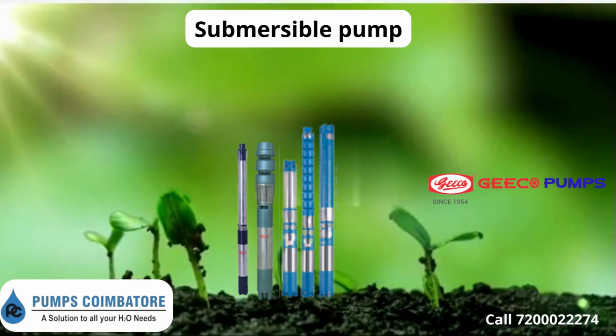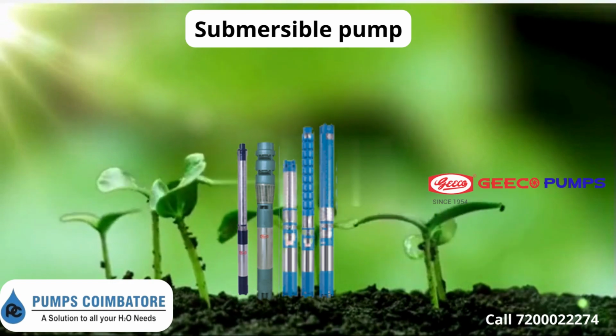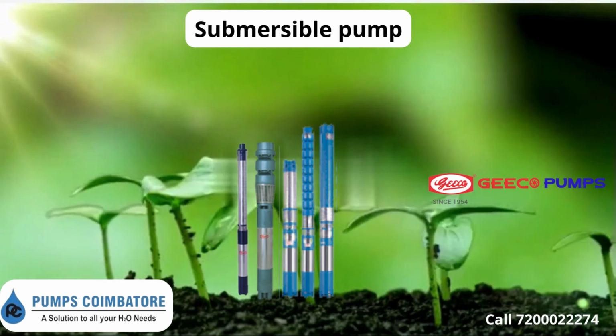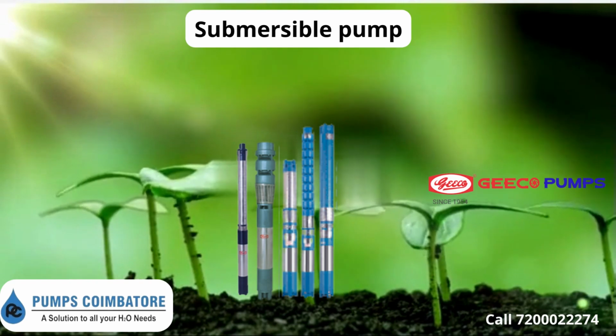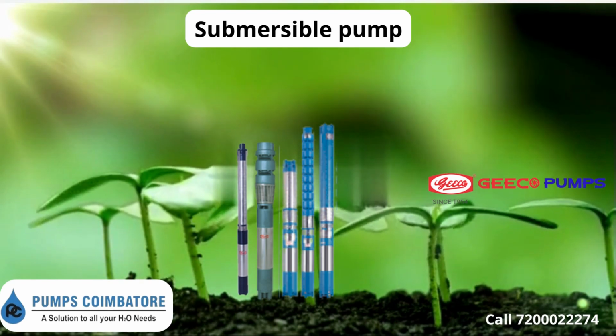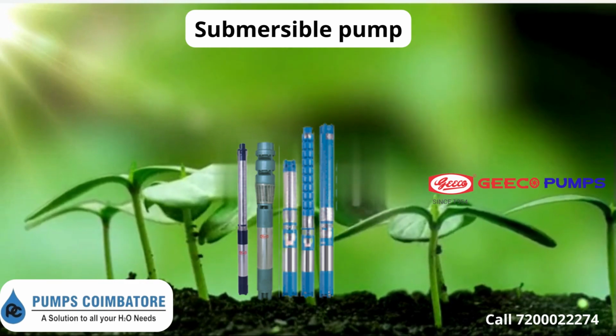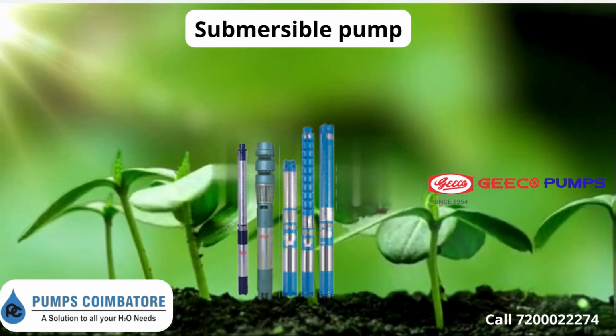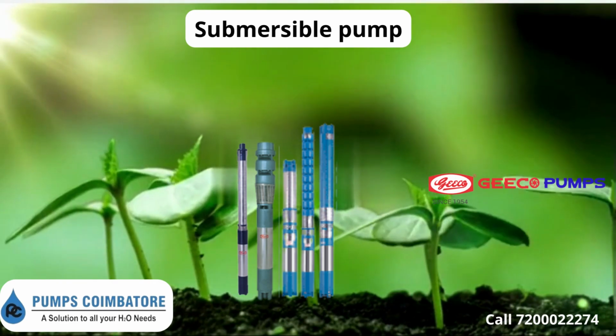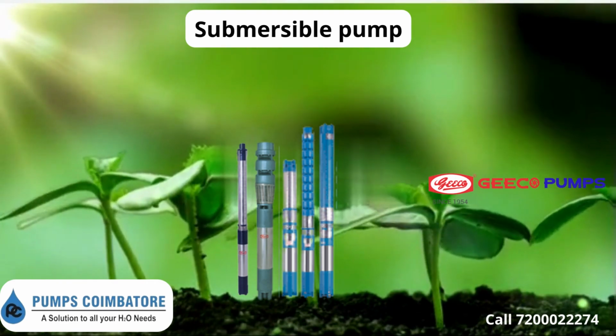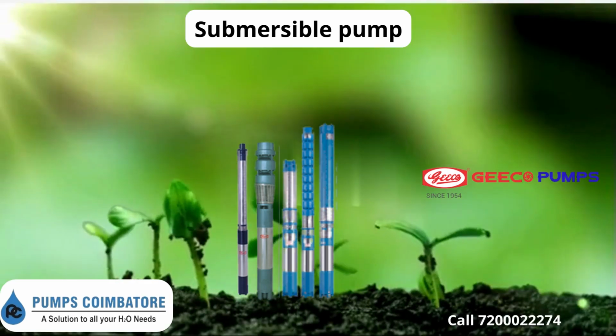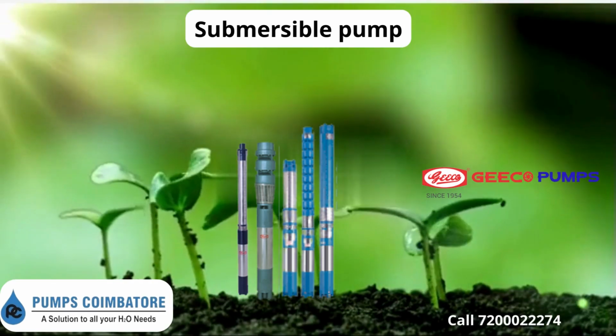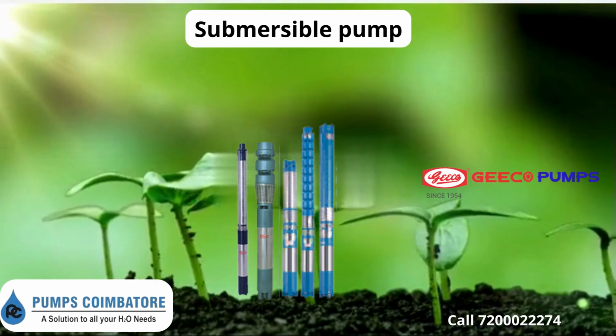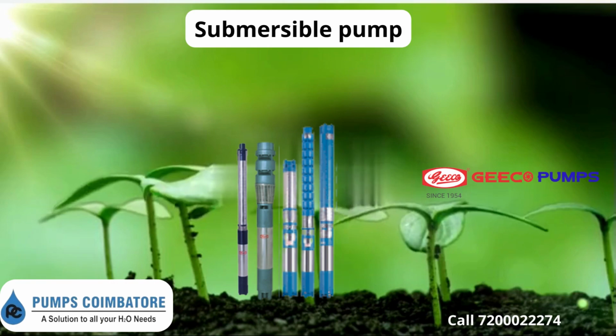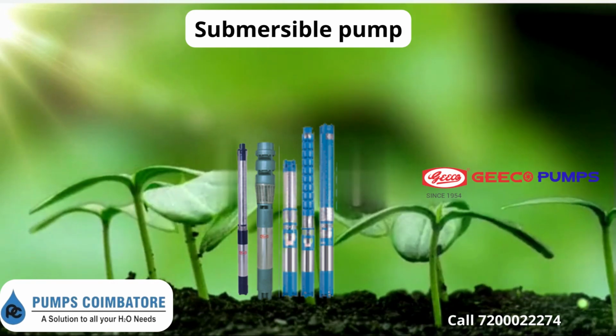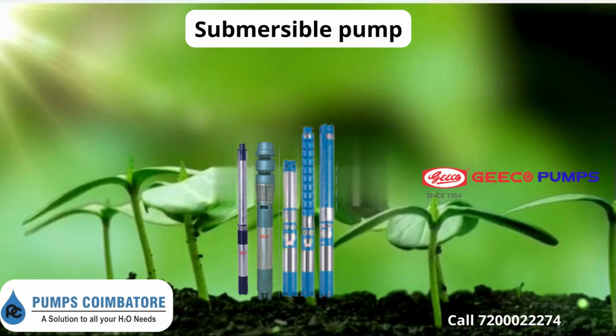In agricultural irrigation applications, a submersible pump is a turbine pump close coupled to a watertight electric motor, which eliminates the long drive shaft and bearing retainers needed for a deep well turbine pump. The pump is above the motor and water enters the pump through a screen between the pump and the motor. Because submersible pumps are smaller in diameter, they are lower in efficiency than those used for centrifugal or deep well turbine pumps. The motor may overheat or burn out if the circulation of water past the motor is restricted or inadequate. The length of riser pipe must be enough to keep the bowl assembly and motor submerged at all times. Also, the well casing must be large enough to allow water to flow past the motor.